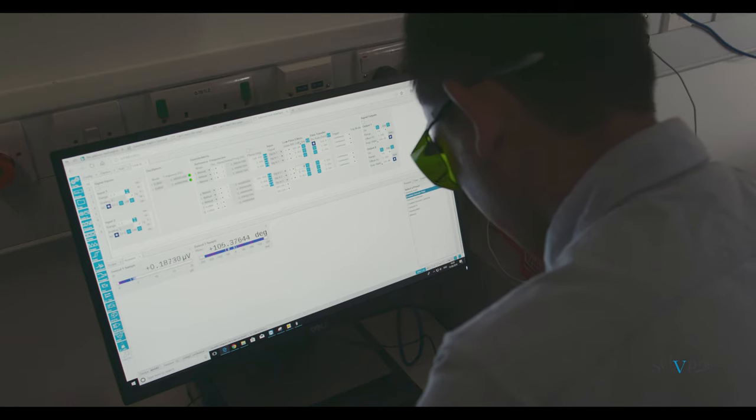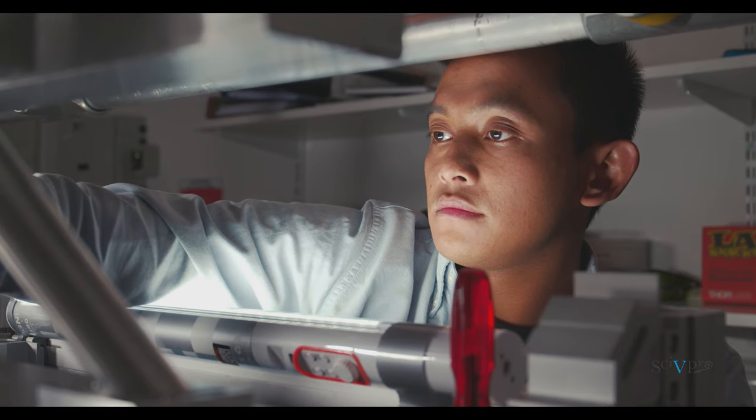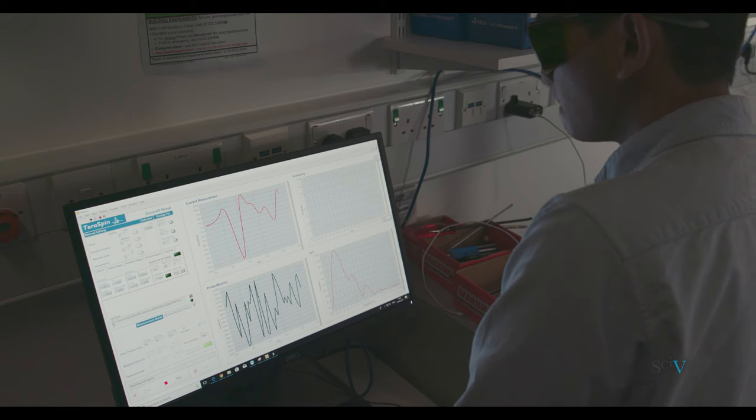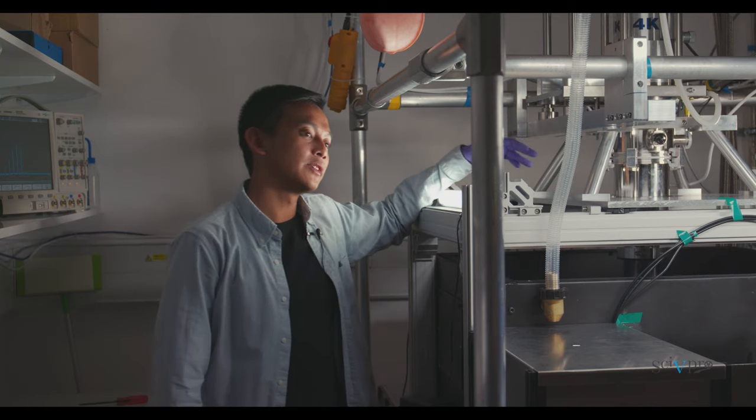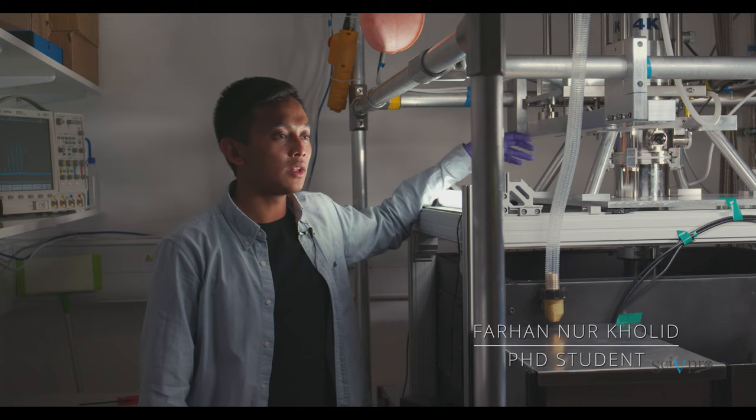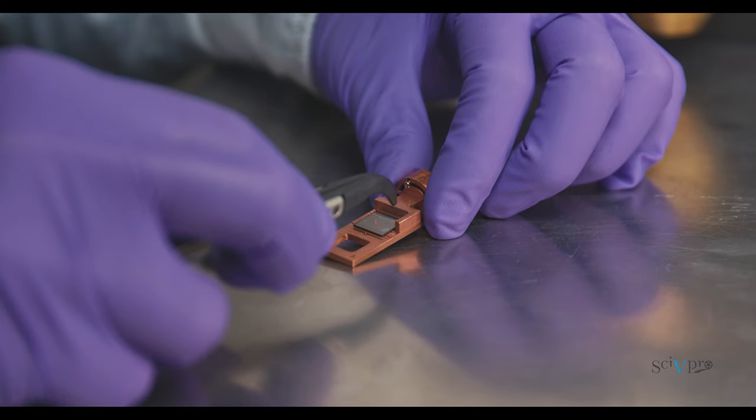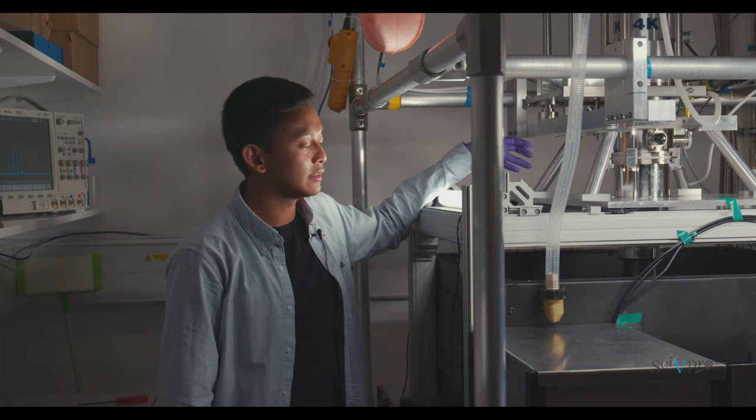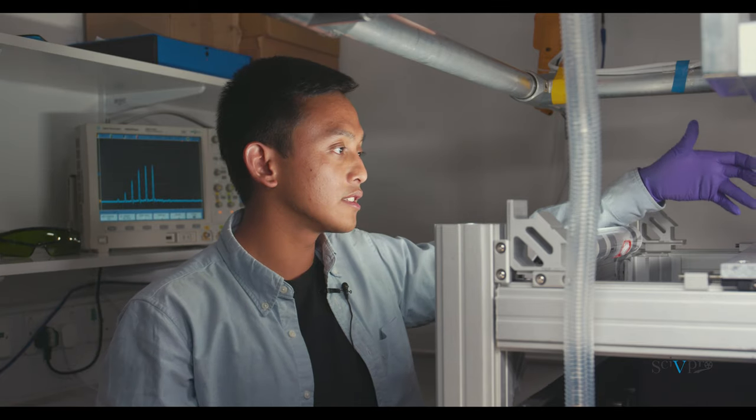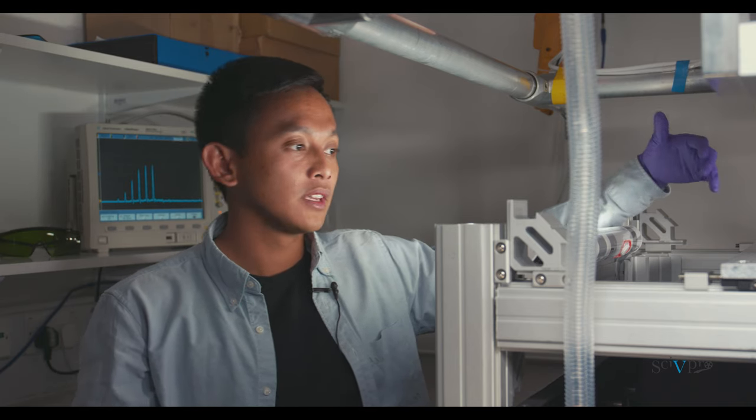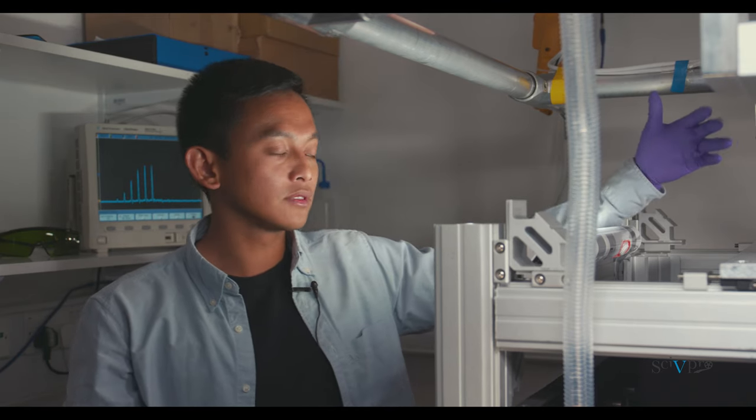In this section, we illustrate how to run a calibration measurement in emission mode with the terahertz time domain spectroscopy setup. In this experiment, the sample under test is a cobalt and platinum thin film bilayer. We choose this structure as our calibration sample mainly because it gives very strong terahertz emission. It's a well-characterized terahertz spintronic emitter that gives you broadband terahertz up to 30 terahertz.